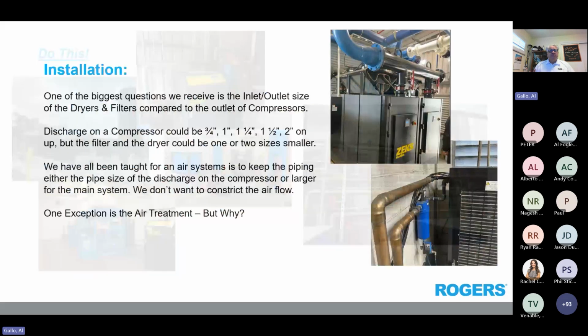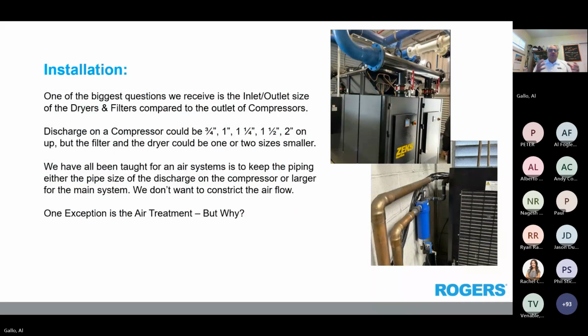So putting some thought into how we need to run everything is really important. And that's where I think laying out the equipment, either on paper or in the room, is extremely important. One of the most common questions we get is, my compressor is this size, my air treatment is this size, why aren't they all the same size for the same flows and pressures and whatnot? We've all been taught to keep the airlines as big as whatever the outgoing compressor is, or bigger. So if it's 1.5 inches coming out, we want to keep it a minimum of 1.5 inches going through everything.